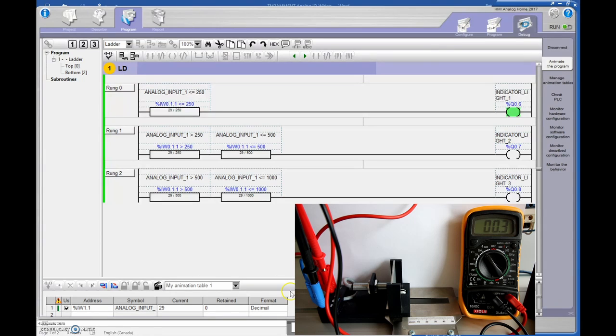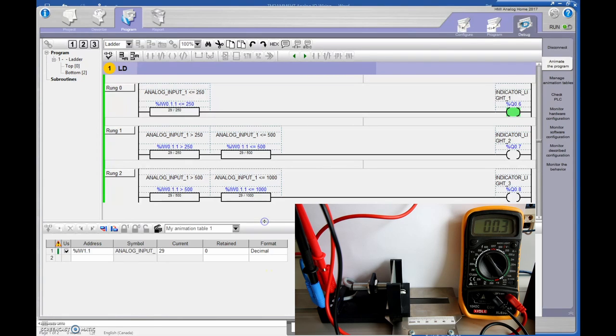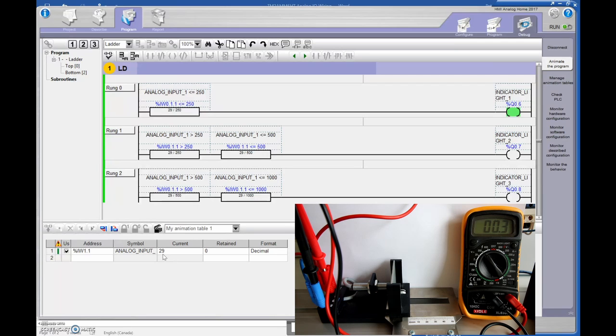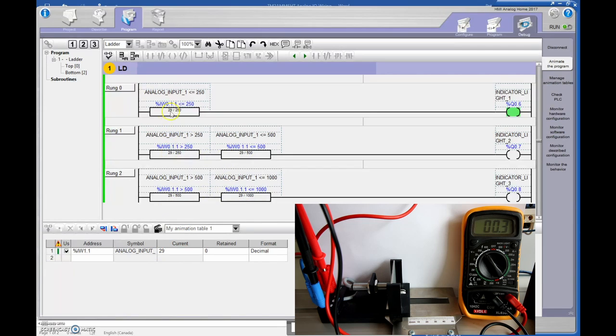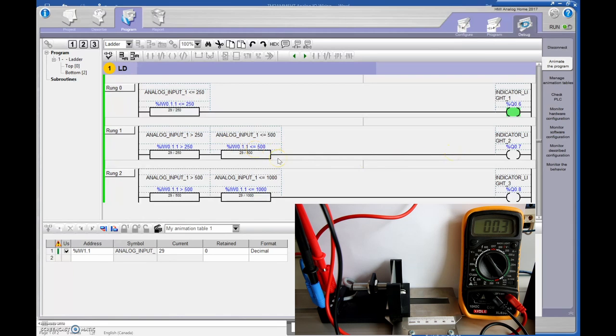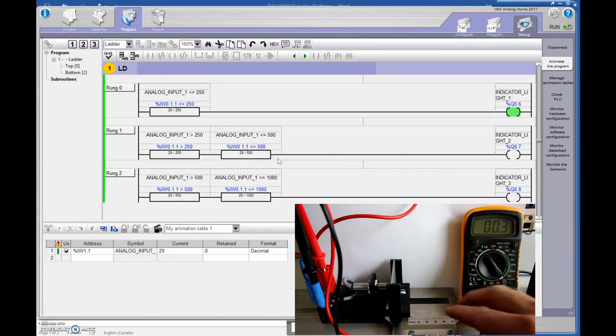And you'll see that this value right here, this value right here that is similar on every one of my inputs there, that's looking at my input from my analog card. If I want to look at the animation tables, then I'll bring them up here. Easy now. So I cleaned this up. Sorry, I had all that forward reverse stuff on there before. So now we just have that analog input. And we can see that this value right here, 29, matches with what's on the voltmeter there. So 0.3 is the same as like 0.29. So now what we're going to do is we're going to slowly increase the distance between the sensor and the piece of steel.